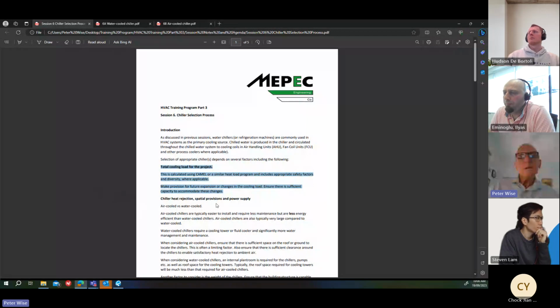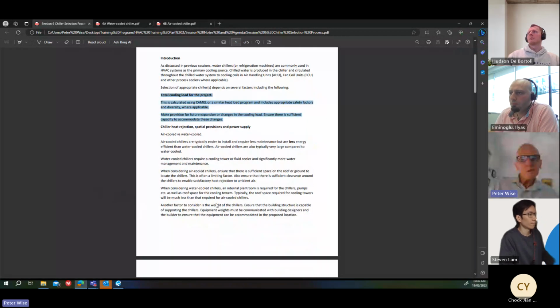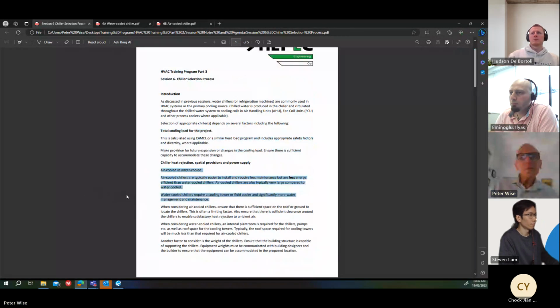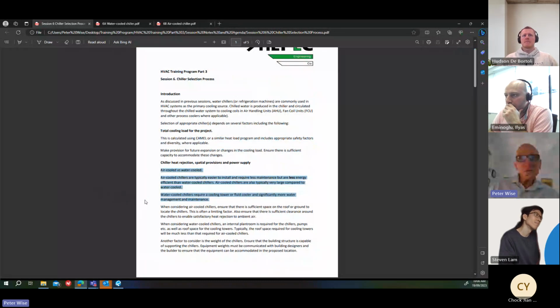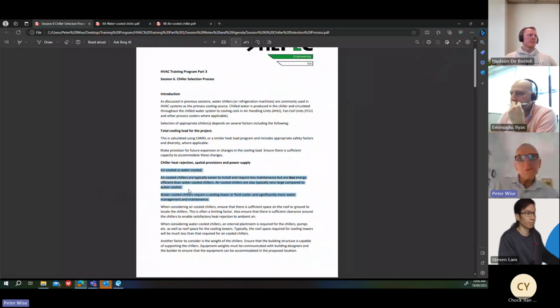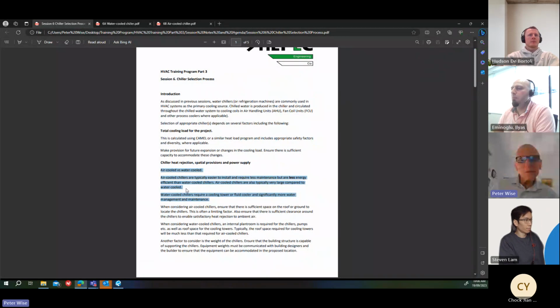Chiller heat rejection, spatial provisions, and power supply. So we've got air-cooled versus water-cooled. Which way are we going to go? Air-cooled chillers are typically easier to install and require less maintenance, but they have less energy efficiency than a water-cooled chiller. So that's always important, but may not be the governing factor for the selection. Air-cooled chillers are also typically very large compared to water-cooled. So an air-cooled chiller, we've talked before about this, generally can get capacities up to about 1,500 kilowatts. Above that, if you're using air-cooled, you'll have multiple chillers.